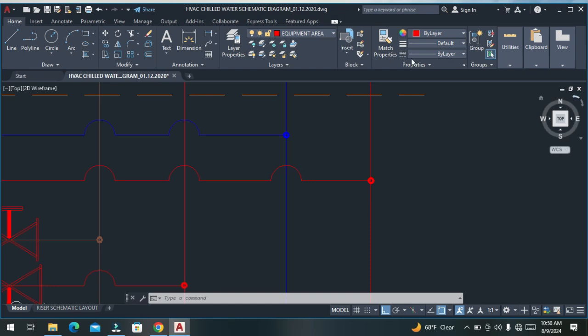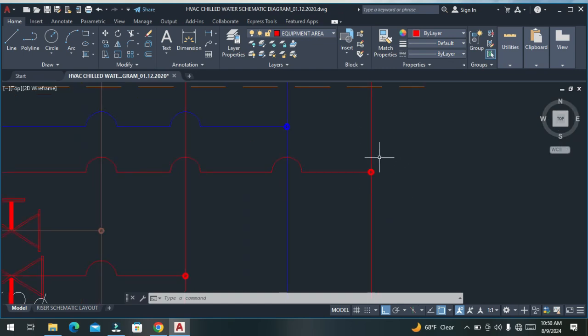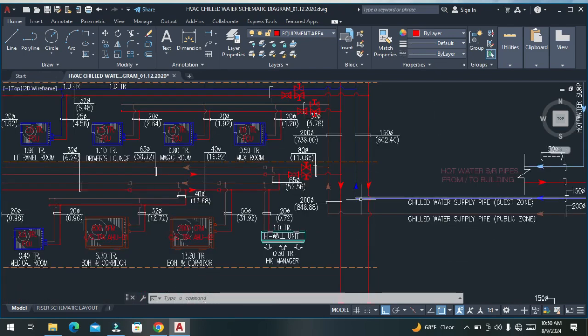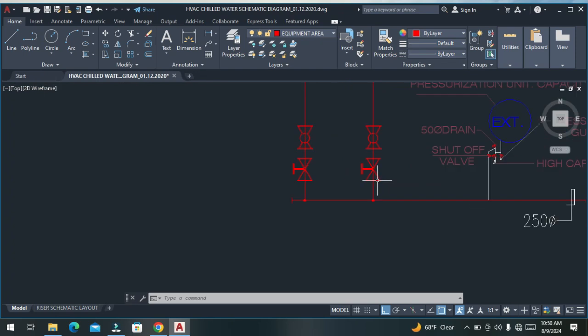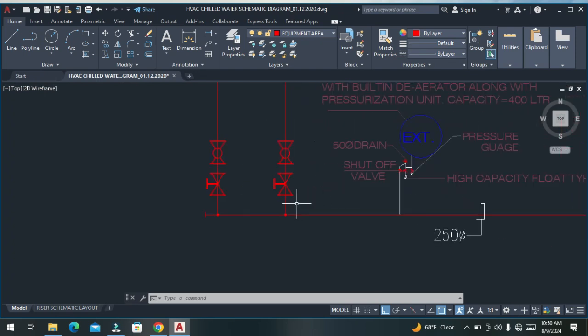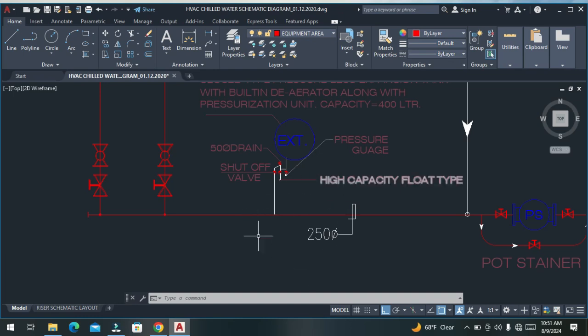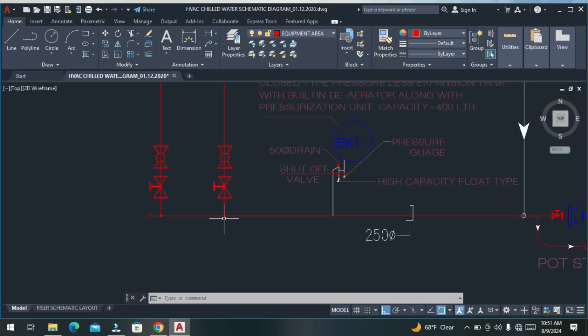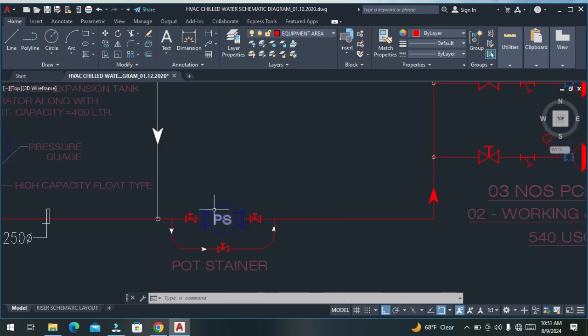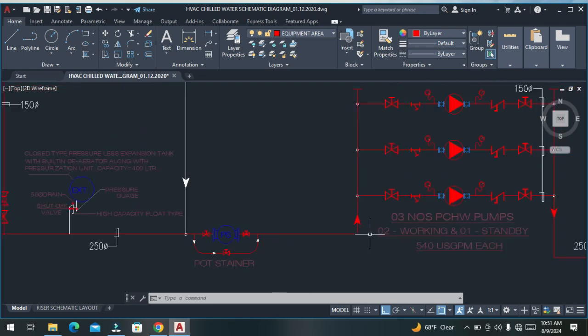So this is actually the chilled water return, and from here it goes, if you follow the direction, towards this header. Here we have a chilled water makeup system with a booster pump. If water gets lost in this closed loop, it will adapt automatically. This return line comes, and this is a strainer, and this is the bypass line. During cleaning we can open this bypass line and use it without interruption during the cleaning. So it will transfer like this, and where does it go?